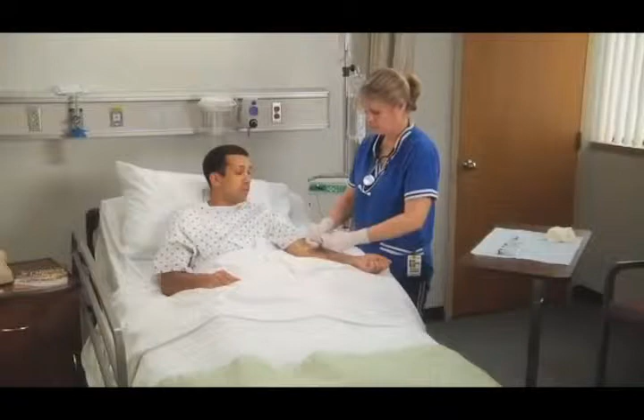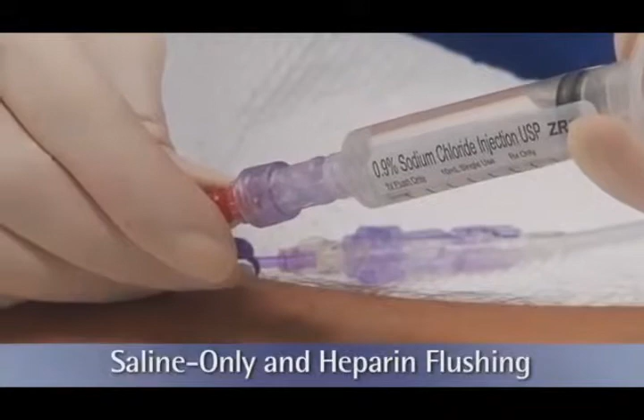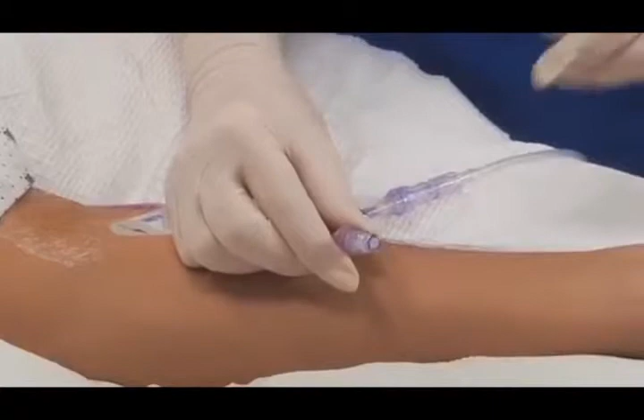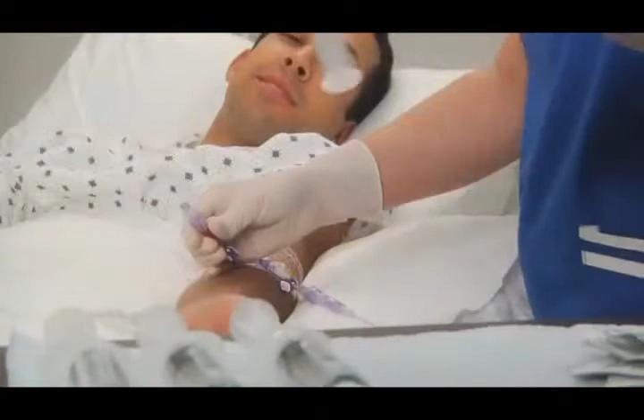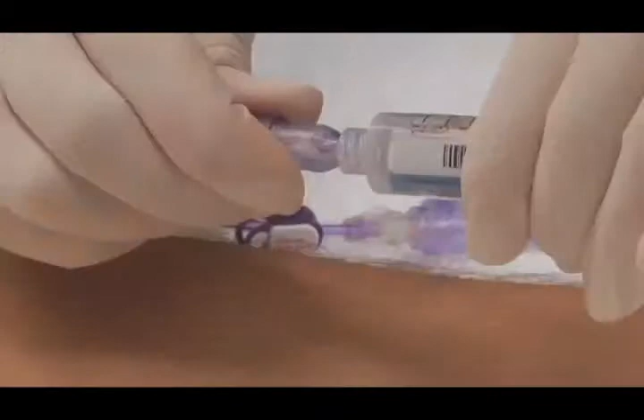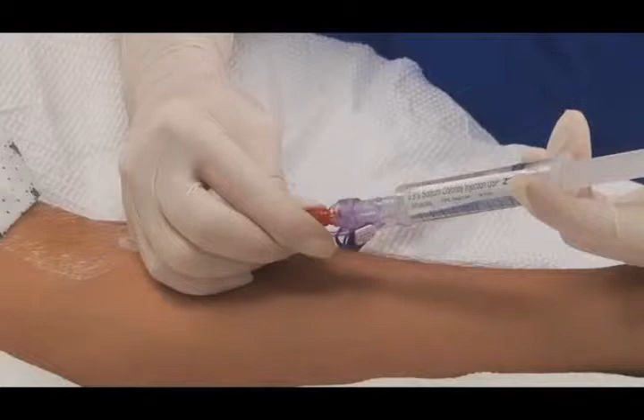After the clinician has properly disinfected the Caresite Luer Access device, she continues the flushing procedure. Caresite supports both saline-only and heparin flushing options to meet any healthcare facility's protocols. If the IV line is clamped according to facility protocol, the clinician unclamps the line. The Luer lock flush syringe is then attached by inserting it directly into the Caresite Luer Access device, turning the syringe clockwise. This Luer connection opens the Caresite flow path, allowing for aspiration, injection, or infusion. Before continuing with the flush procedure, let's look at the internal design of the Caresite Luer Access device.